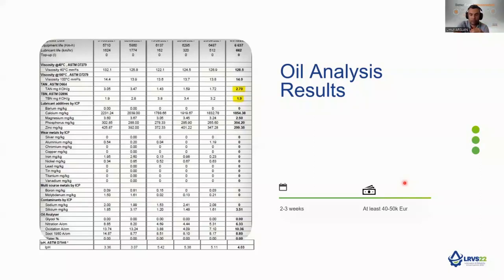Then the gas generator was shut down immediately. If the gas engine had been running for a long time with oxidized oil of increased viscosity, it would have caused damage of at least 40 or 50,000 euros. Imagine that. Or it could result in bearing wiping, abnormal overheating, or piston seizure. In the meantime, the generator plant would not work for about 3 weeks, because it could cause serious damage. That's why we noticed that oil analysis gives an early signal.